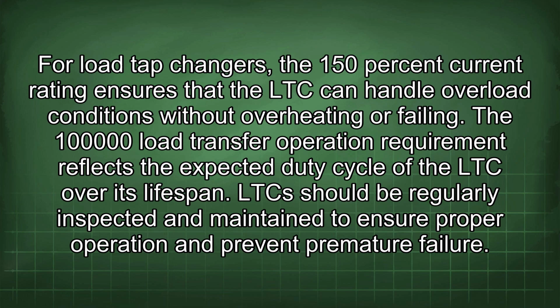For load tap changers, the 150% current rating ensures that the LTC can handle overload conditions without overheating or failing. The 100,000 load transfer operation requirement reflects the expected duty cycle of the LTC over its lifespan. LTCs should be regularly inspected and maintained to ensure proper operation and prevent premature failure.